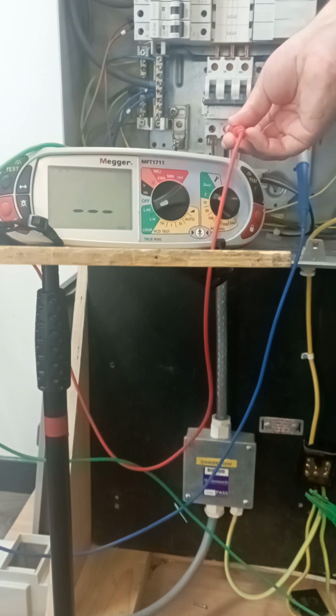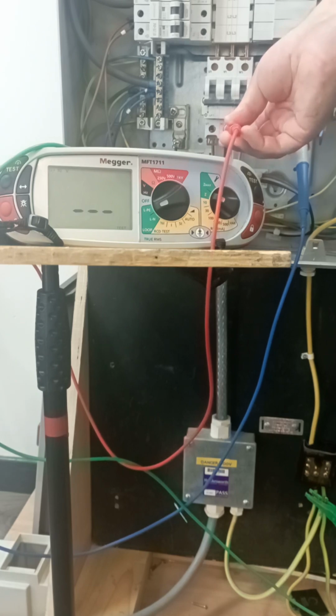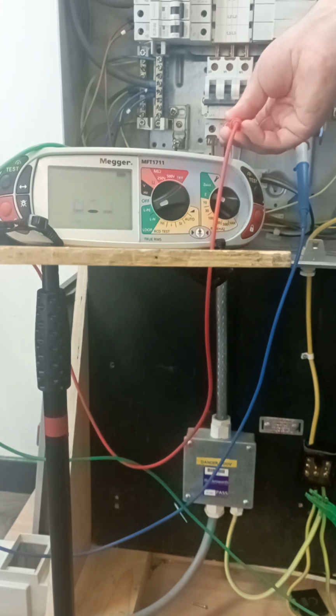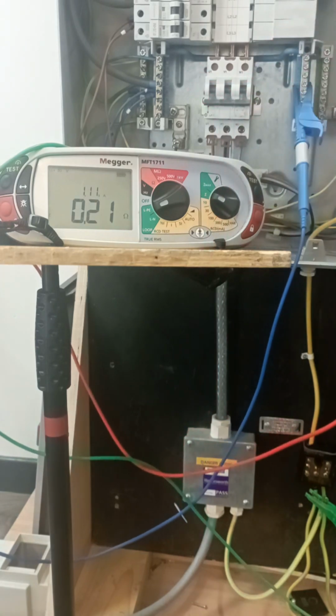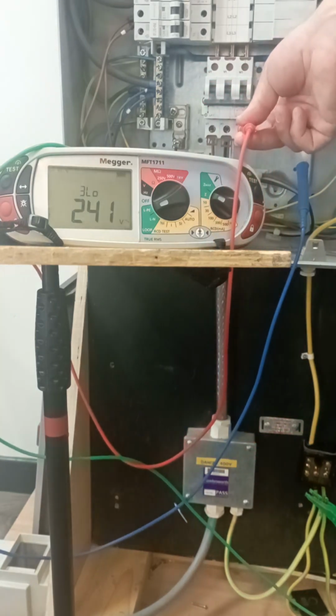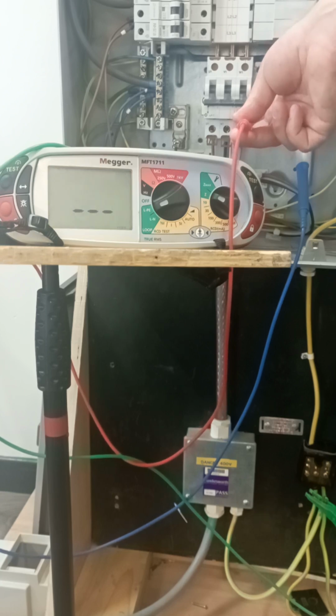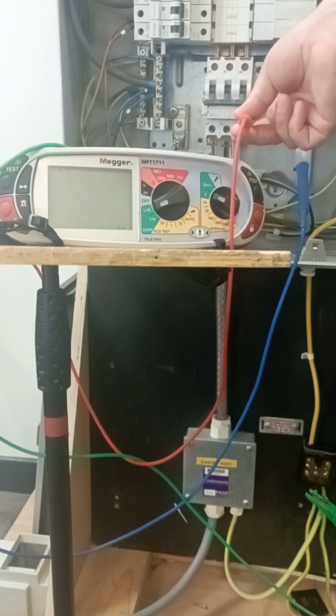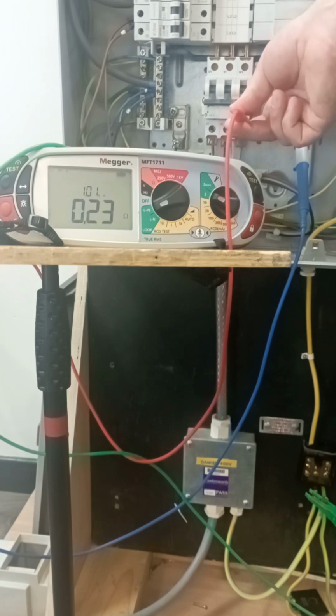So we're going to line 2, up to 240 volts there. 0.21 of an ohm this time. Line 2 off, line 3 on. So you'll see that's us, we've now run through the 3 line conductors, testing purely the earthing conductor for ZE. Now remember, I'm not touching any other exposed or extraneous conductive parts. You might need to use transparent screening, shrouding, things like that to make you a wee bit safer. I've got a big rubber mat under my feet here as well. Okay, so we've 0.23 of an ohm.